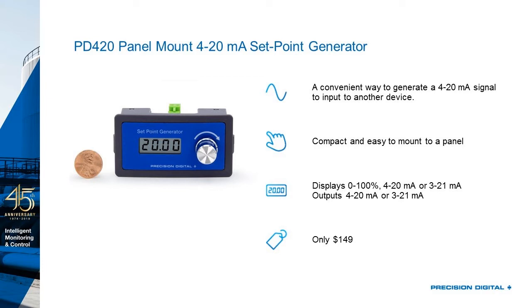This is a great way to get a 4 to 20 milliamp into another device for either a benchtop device where you're going to be using it to prove or test all different kinds of equipment, or even on a panel where you want to be able to switch to a manual mode. This might be sending a 4 to 20 milliamp signal to a valve positioner, a servo, a PLC, or even just being used in a system test to replace the transmitter as a check on the fact that all of your alarms and such are working.